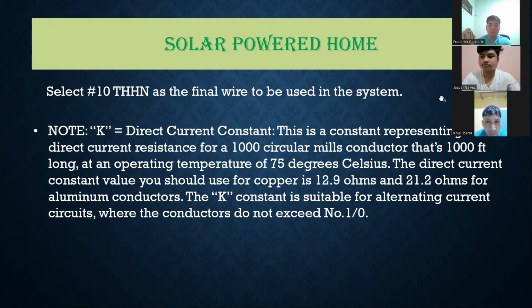As I said before, the K is a direct current constant, which is the constant representing the direct current resistance for a 1,000 circular mils conductor that's 1,000 feet long at an operating temperature of 75 degrees Celsius. The direct current constant value you should use for copper is 12.9 ohms. That's where we got the 12.9 value from before. And 21.2 for aluminum. The K constant is suitable for alternating circuits where the conductor does not exceed number 1/0.